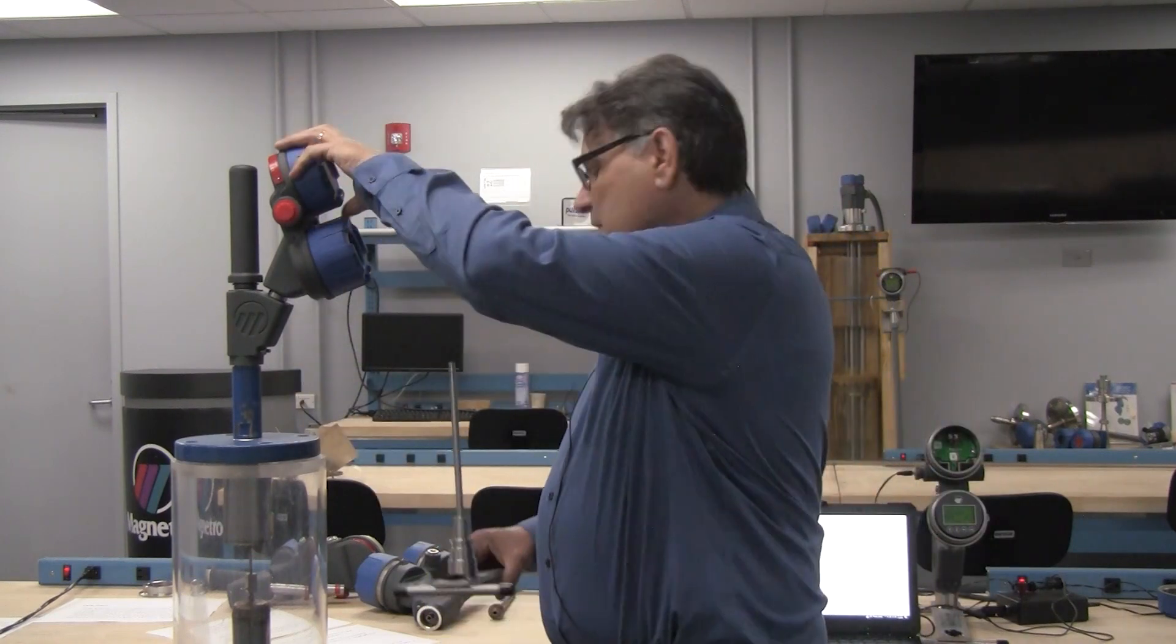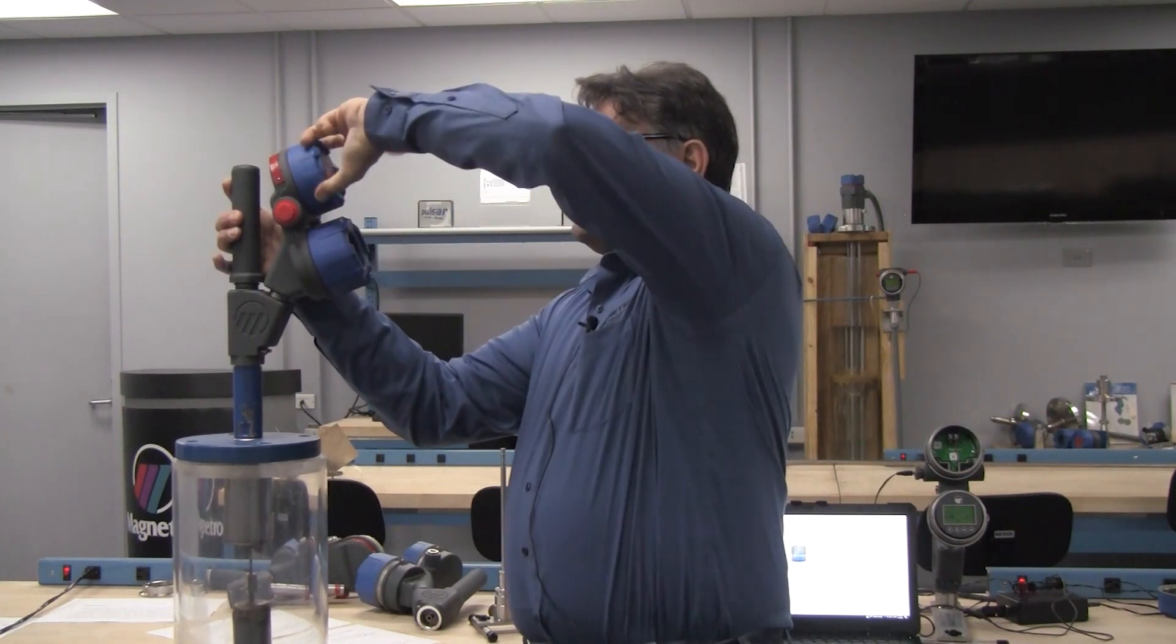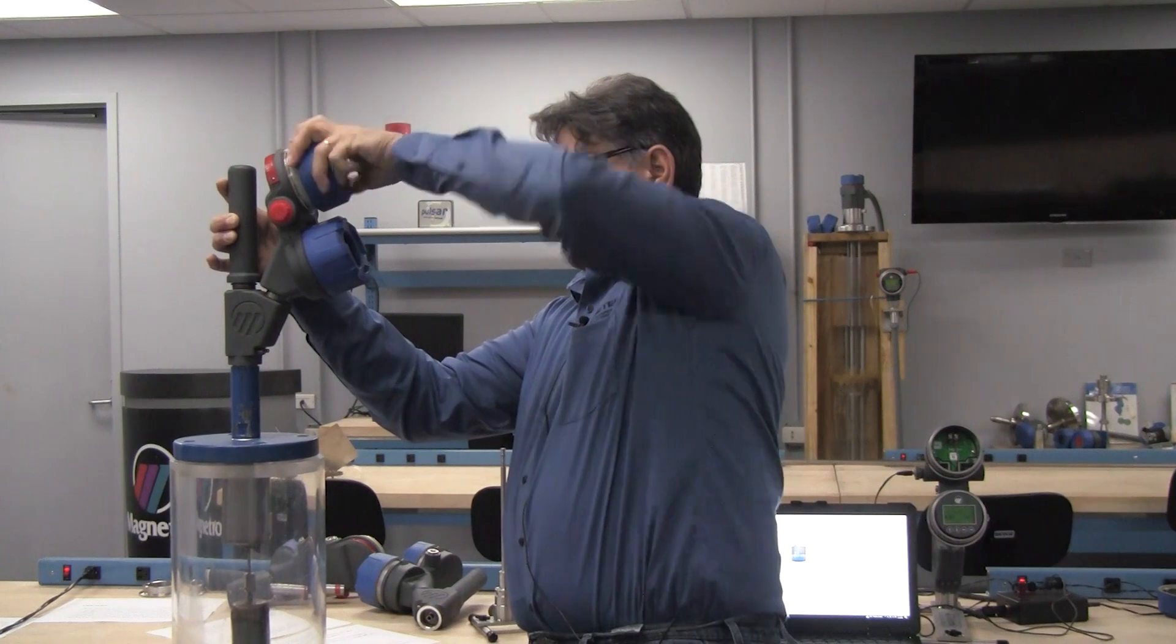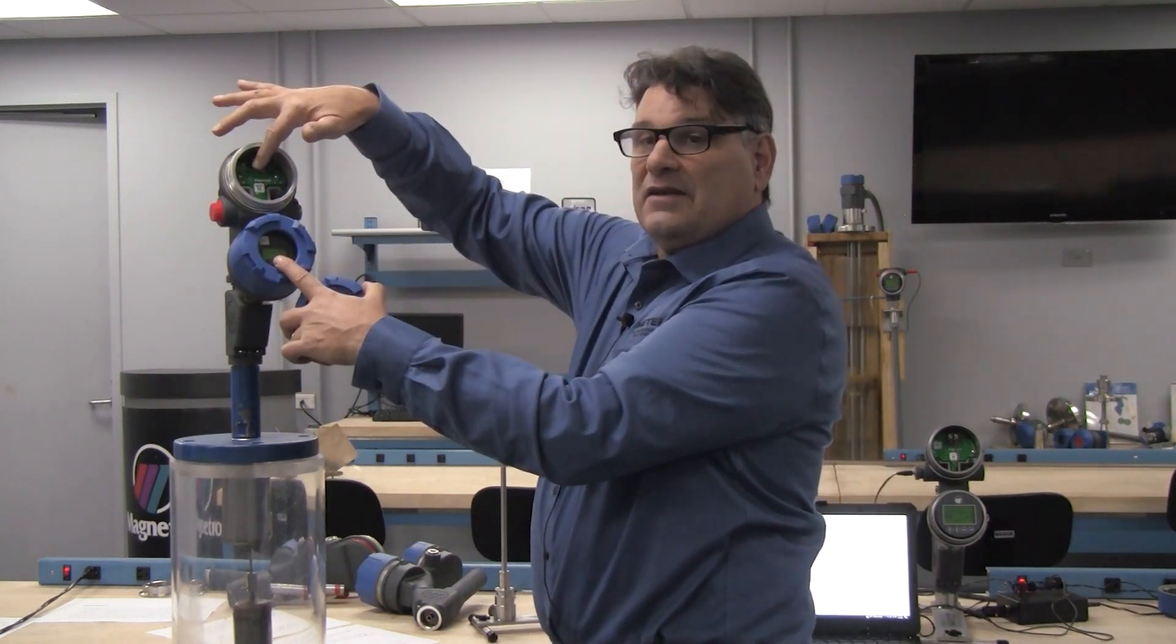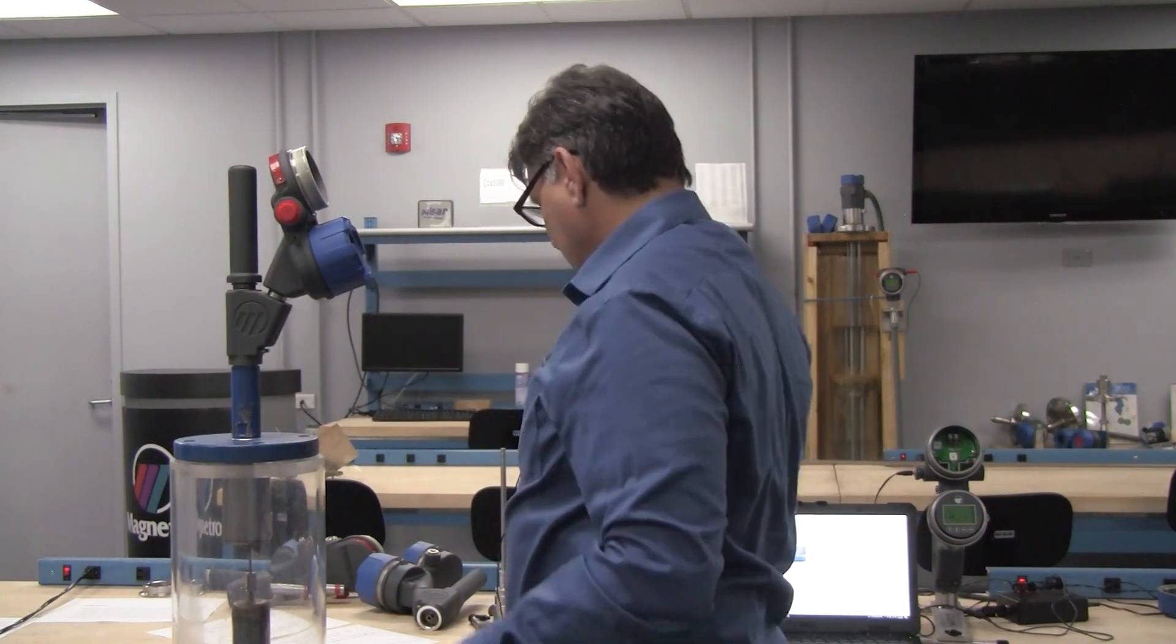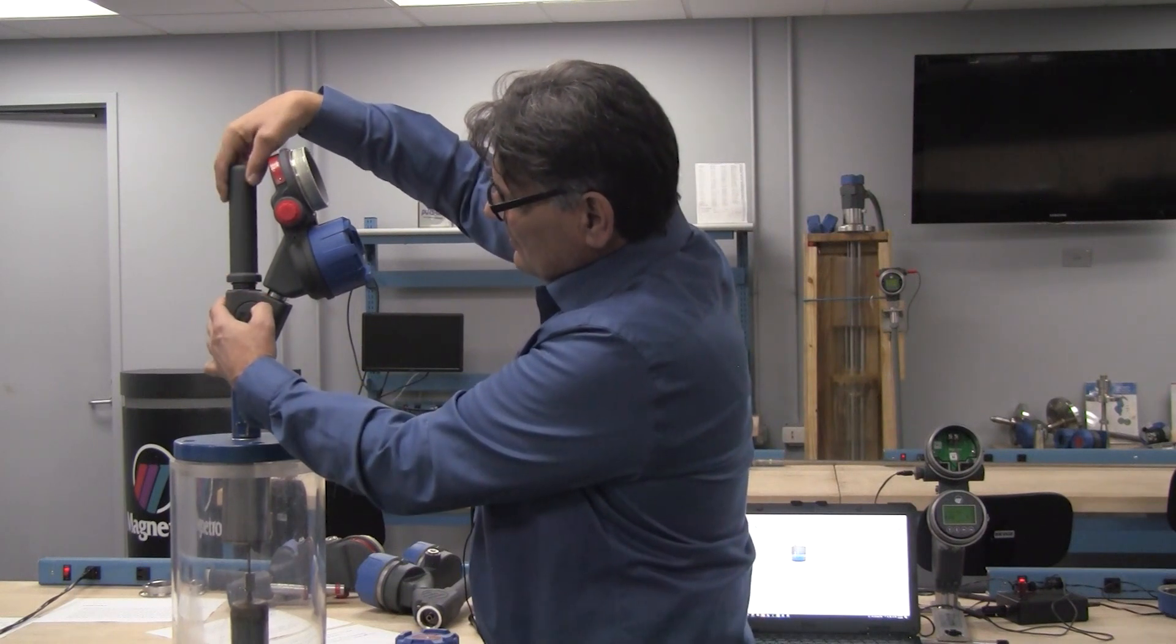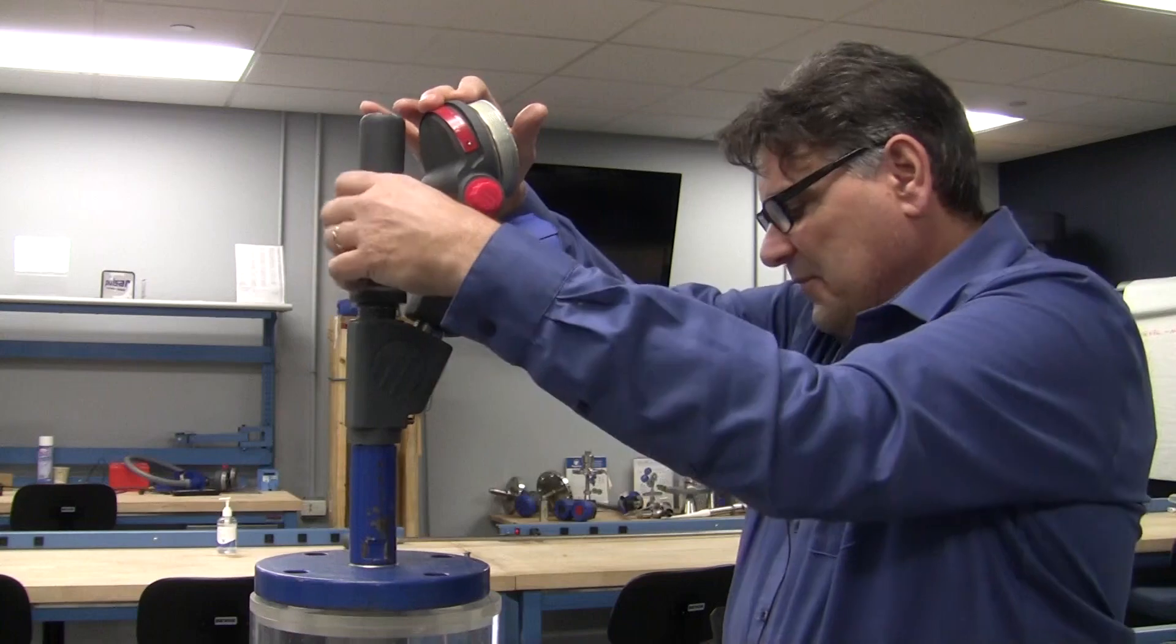We're going to start by removing the old housing. You can start by powering down your old transmitter, remove the cover, top cover, and disconnect your wiring leads. After you have your wiring leads disconnected and pulled out of the transmitter, you're then going to remove the cover from the LVDT.